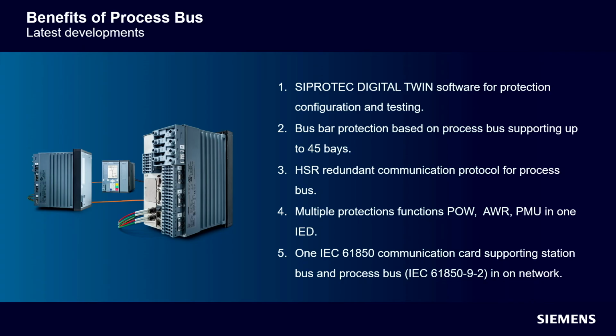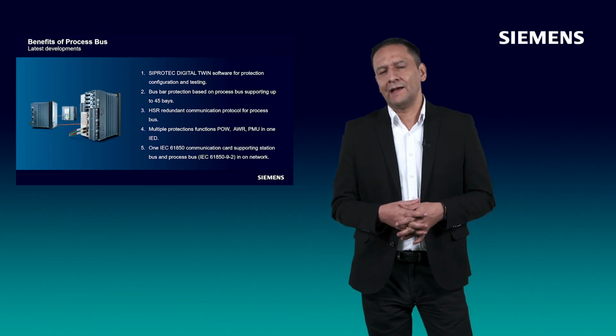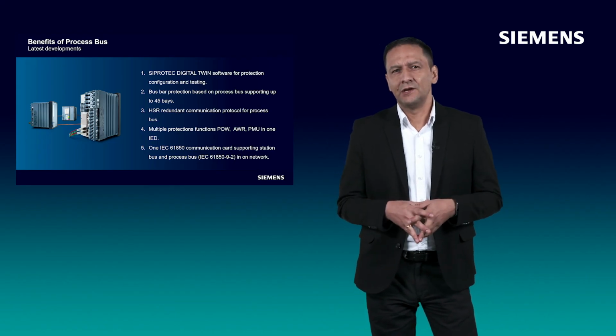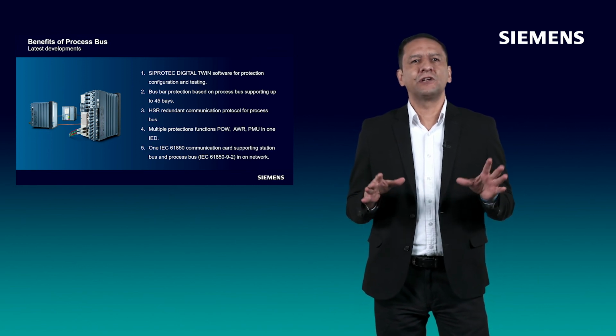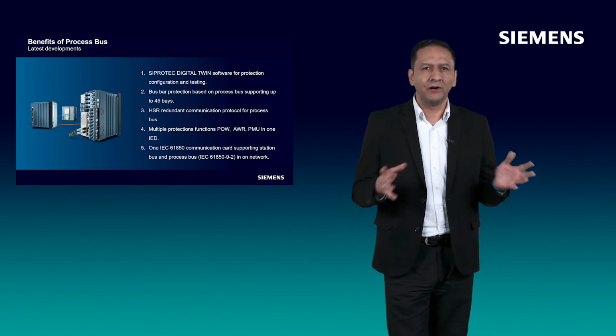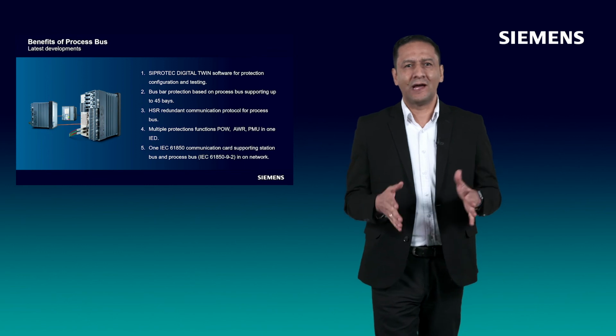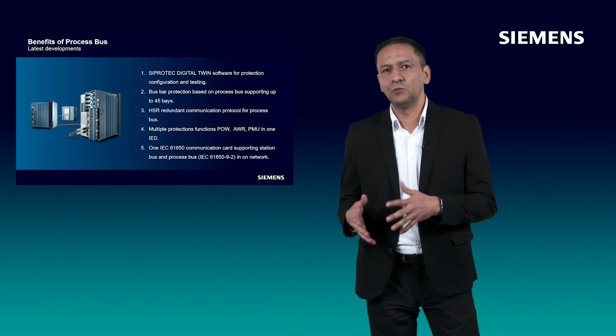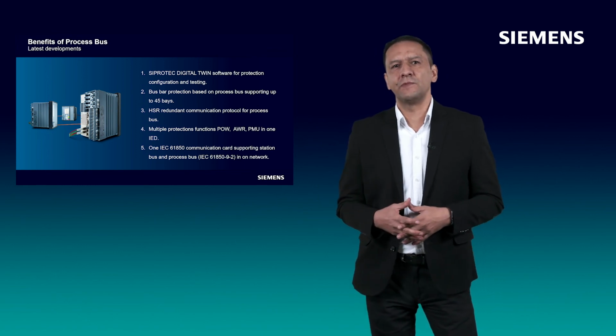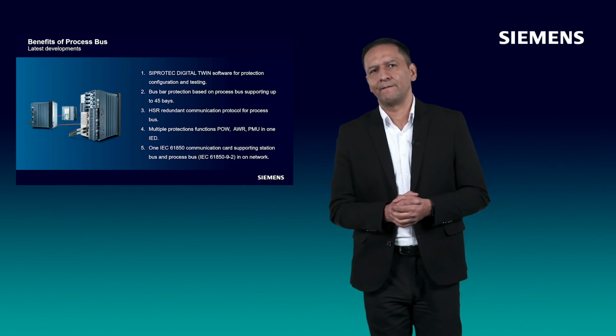Also, we can have multiple protection functions like overcurrent protection and also multiple control functions like point on wave, automatic voltage regulation, and phasor measurement unit in one device. And last but not least, one IEC 61850 communication card supports station bus and process bus based on IEC 61850-9-2, as well as phasor measurement unit in one network.